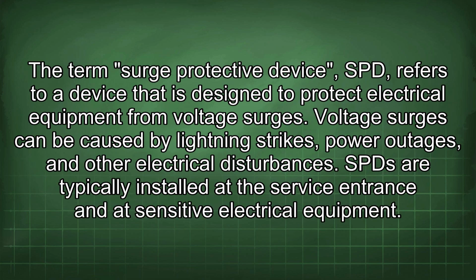The term surge protective device (SPD) refers to a device that is designed to protect electrical equipment from voltage surges. Voltage surges can be caused by lightning strikes, power outages, and other electrical disturbances. SPDs are typically installed at the service entrance and at sensitive electrical equipment.